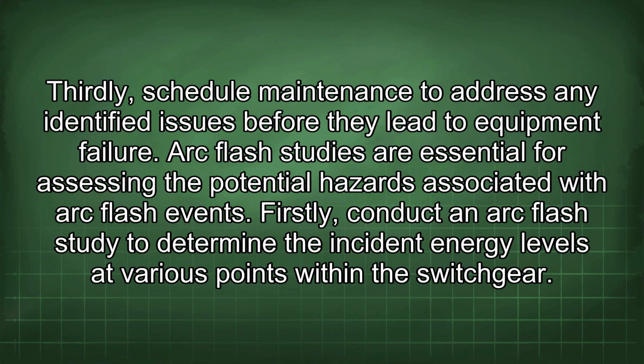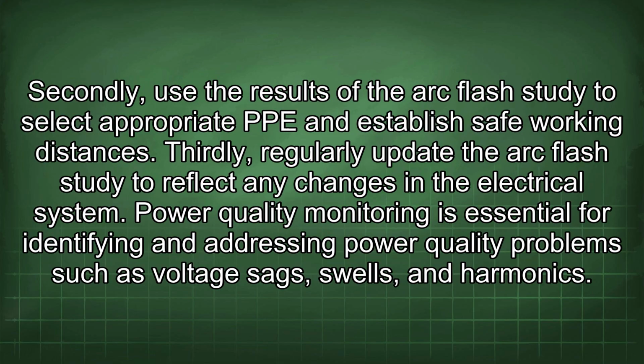Arc flash studies are essential for assessing the potential hazards associated with arc flash events. Firstly, conduct an arc flash study to determine the incident energy levels at various points within the switchgear. Secondly, use the results of the arc flash study to select appropriate PPE and establish safe working distances. Thirdly, regularly update the arc flash study to reflect any changes in the electrical system.